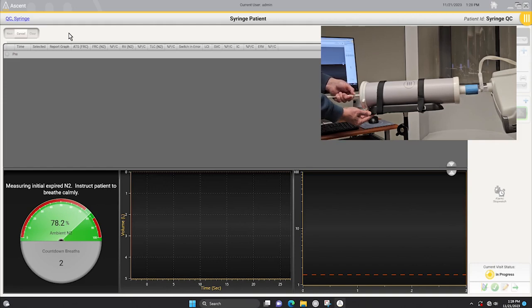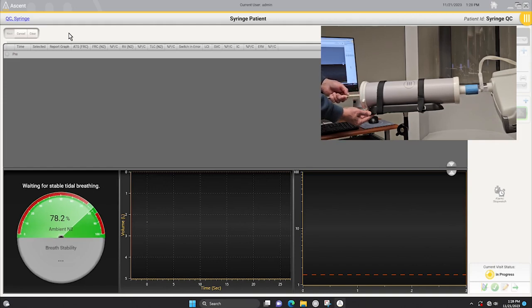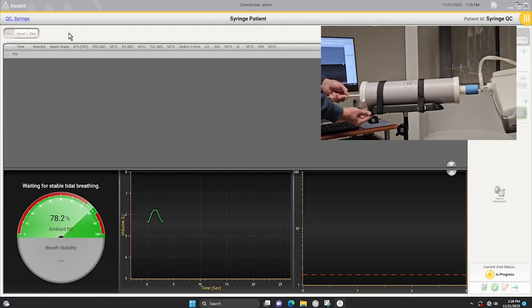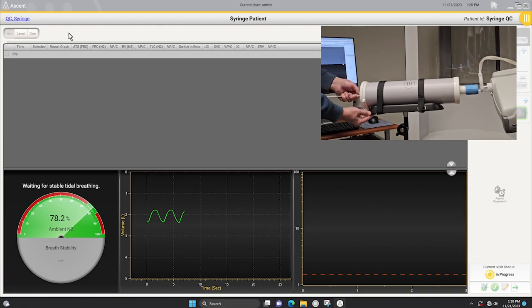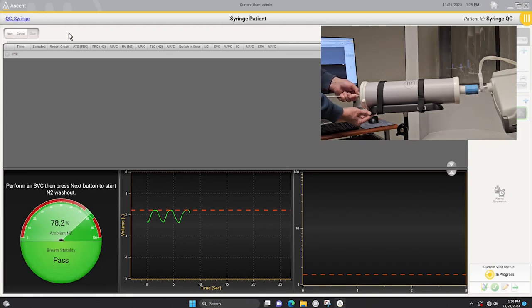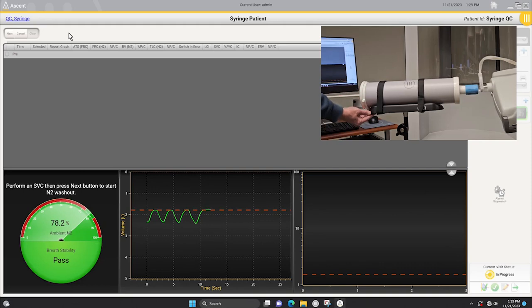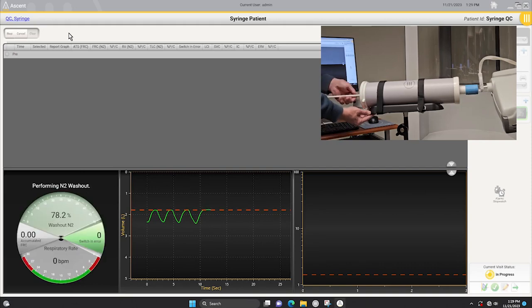After the initial tidal breaths, the volume time graph will trace the tidal breaths. When four stable tidal breaths have been established as indicated by the red horizontal dotted line at the end of exhalation, press the space bar to switch you into breathing 100% oxygen.